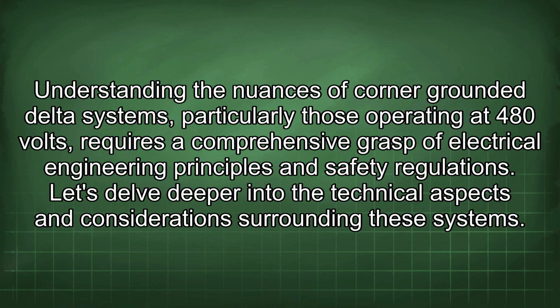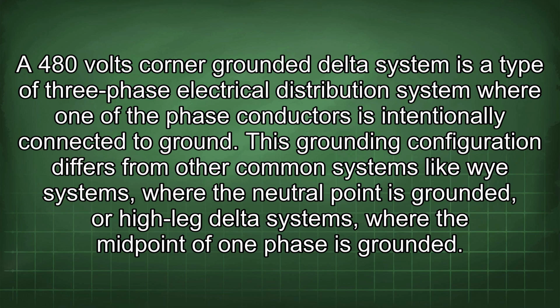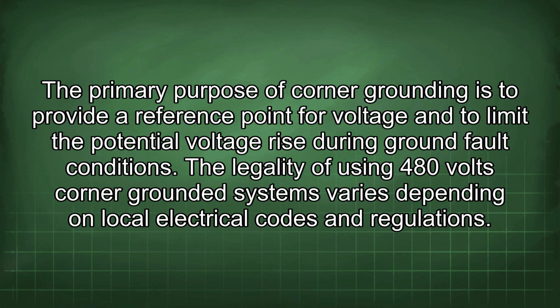Understanding the nuances of corner-grounded delta systems, particularly those operating at 480 volts, requires a comprehensive grasp of electrical engineering principles and safety regulations. Let's delve deeper into the technical aspects and considerations surrounding these systems. A 480 volts corner-grounded delta system is a type of three-phase electrical distribution system where one of the phase conductors is intentionally connected to ground. This grounding configuration differs from other common systems like Y systems, where the neutral point is grounded, or high-leg delta systems, where the midpoint of one phase is grounded. The primary purpose of corner grounding is to provide a reference point for voltage and to limit the potential voltage rise during ground fault conditions.